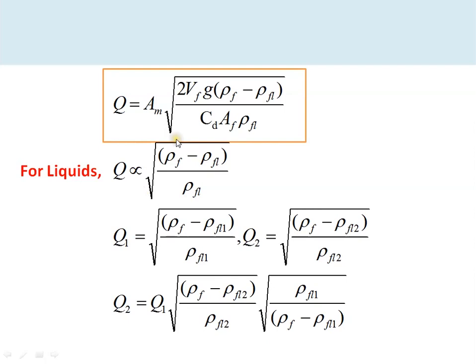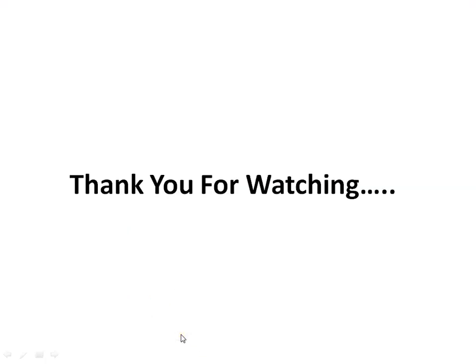When using a rotameter for liquids with a different medium than the calibrated one, the correction equation is different. For liquids, the liquid density is not negligible compared to the float density, so the full expression is used: Q is proportional to √[(ρ_float − ρ_liquid) / ρ_liquid]. The corrected flow rate is: Q_new = Q_1 × √[(ρ_float − ρ_liquid_new) / ρ_liquid_new] × √[(ρ_liquid_cal) / (ρ_float − ρ_liquid_cal)]. Whenever a liquid other than the calibrated liquid is used, this correction must be applied.